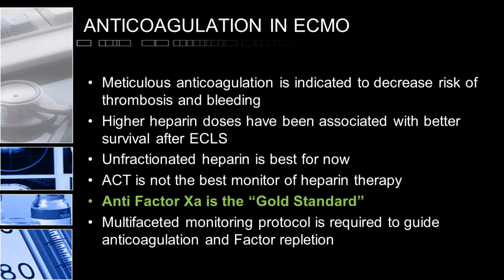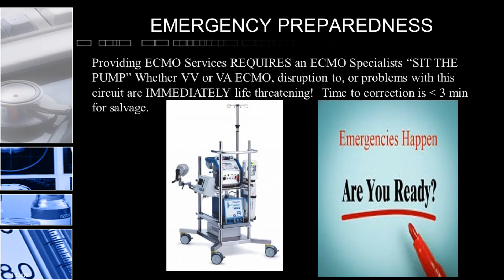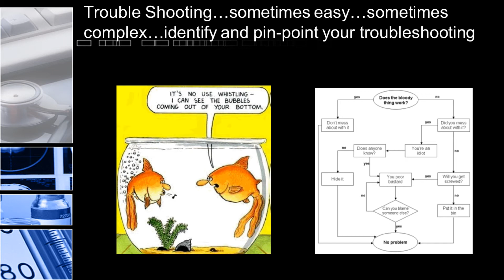One of the biggest considerations in providing an ECMO service is having at the bedside the ability to respond to an emergency. Providing ECMO services requires an ECMO specialist, quote, sit the pump, whether veno-venous ECMO or venous arterial ECMO. Disruption to or problems with this circuit are immediately life-threatening. Time to correction is less than 3 minutes for successful salvage in most circumstances. Although humorously displayed in this slide, the ability of the bedside ECMO specialist to troubleshoot oftentimes makes the difference between having a successful or unsuccessful ECMO program.